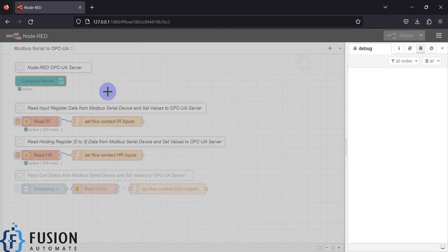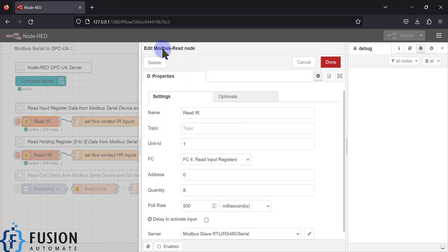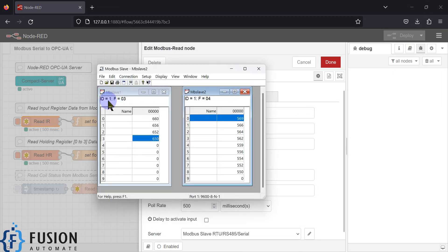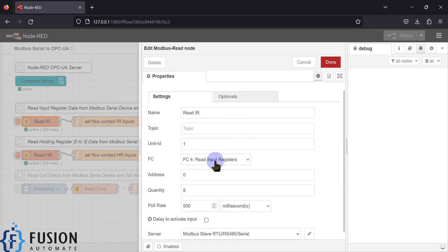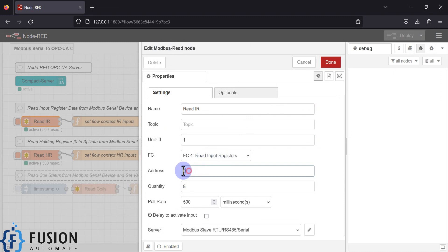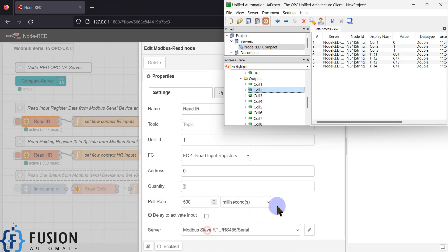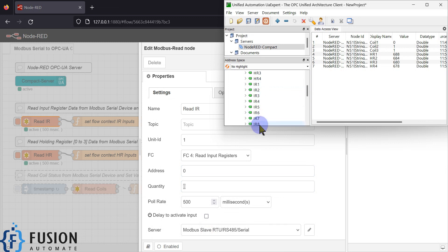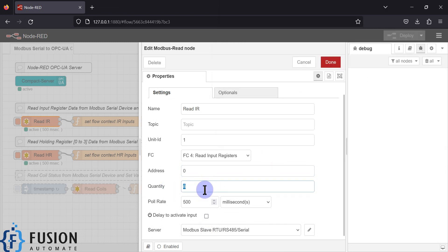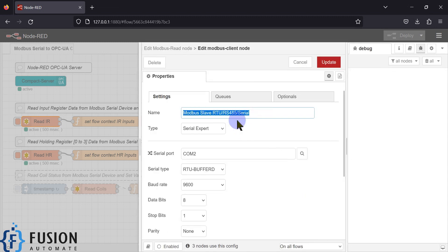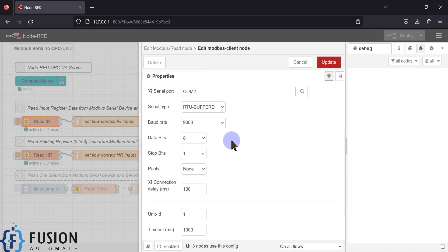Now we will see how I created this. First we'll start with the Modbus nodes. This is the Modbus read node. This node is going to read the input register data from unit ID 1, as you can see. We are going to read the input register starting at address 0 with a quantity of 8, which is why I'm only seeing IR 1 to 8 here. Then there is a polling rate — I want to read the data every 500 milliseconds. And here is our Modbus serial device configuration. If you click the pencil icon, this is my Modbus slave serial device, with type set to serial.